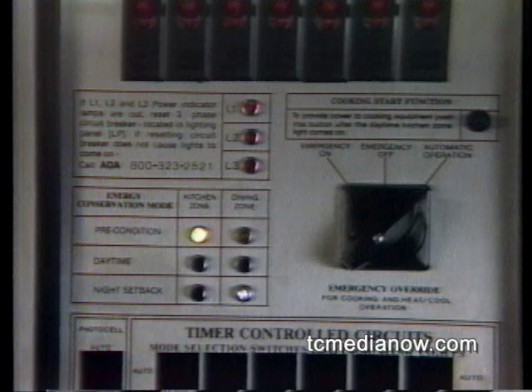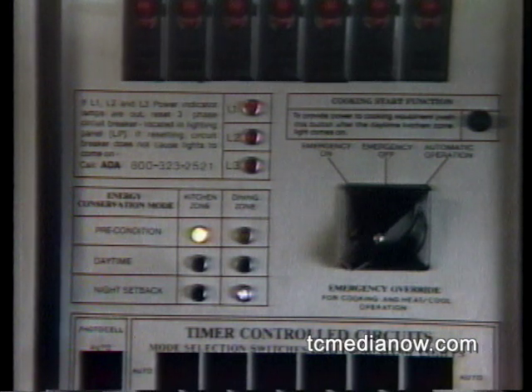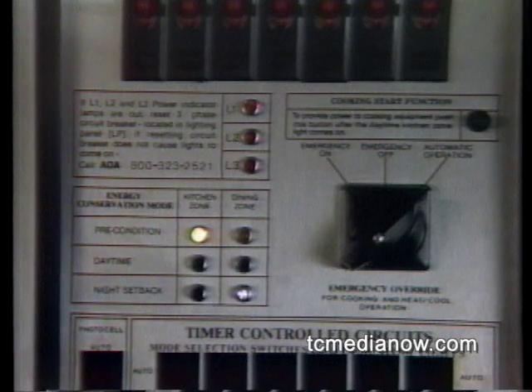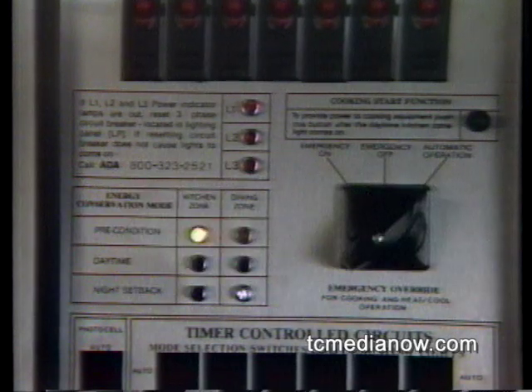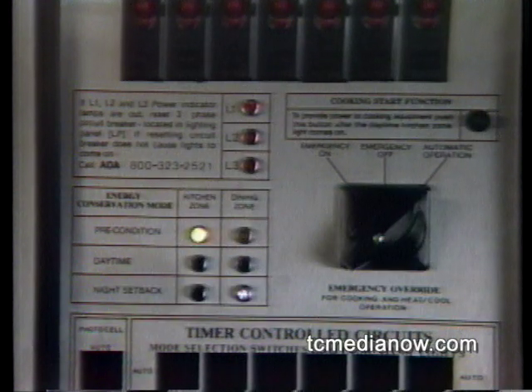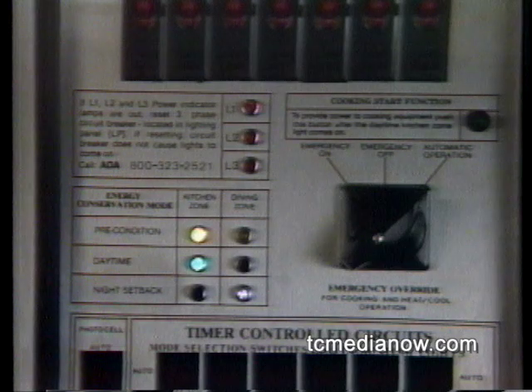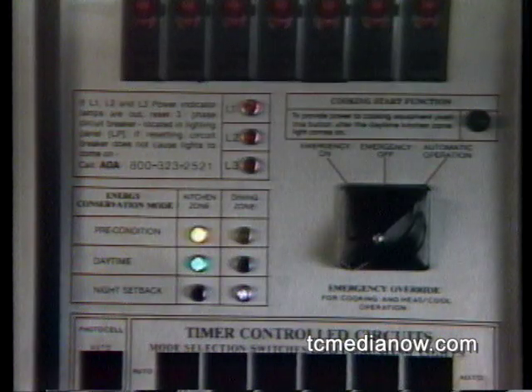About 90 minutes before opening time, the system puts the kitchen into precondition mode. This allows half the kitchen HVAC equipment to function, and the kitchen will now begin to heat or cool. 45 minutes before opening time, the system signals it is time for the kitchen to go into the daytime mode by lighting the kitchen daytime status light. However, the precondition light remains on, and the kitchen will not go into daytime mode until you push the cooking start function button, here.